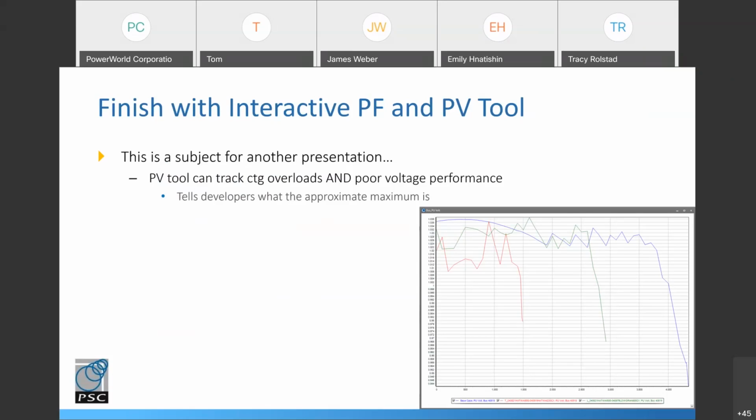There's a lot of reactive control in the area of Hatway, and so you see all this jagginess. But what I've got here is I've run 2 contingencies and the base case. We start out with the base case, that's the blue line, and it just motors on out to some ridiculous number like 4,500. And then this is me interconnecting a generator at the 230 bus at Hatway. You can see that the transformer is the limiting element there. You start cranking it up, and then some reactive device switches in. There's reactors out there. There's capacitors in the area. You end up with this kind of jagginess, and then suddenly you reach the cliff and you go over.